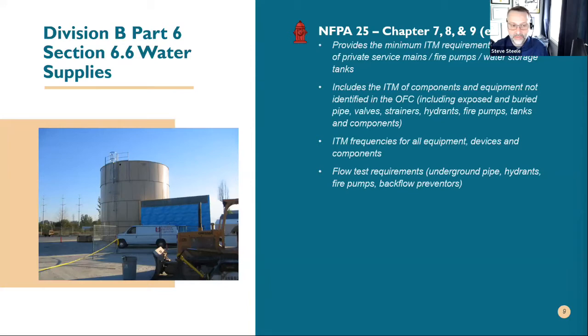So you ensure that it works and protects the municipal system, but what you haven't done is your full forward flow test on it, to see that with that device on there, the fire protection system will still function. So there are additional tests. You may have a duplication of testing here and qualifications to do those tests. That's also true with TSSA and the fuel systems for a diesel fire pump. Again, topics probably for another day, but that will be coming as well. You have TSSA requirements, but now you have NFPA 20 requirements that are a lot more encompassing than what I'm talking about with backflow preventers, that may in some cases contravene what TSSA is looking for and the qualifications to do so. So you may be looking at additional coordination with some of those regulatory authorities as well.